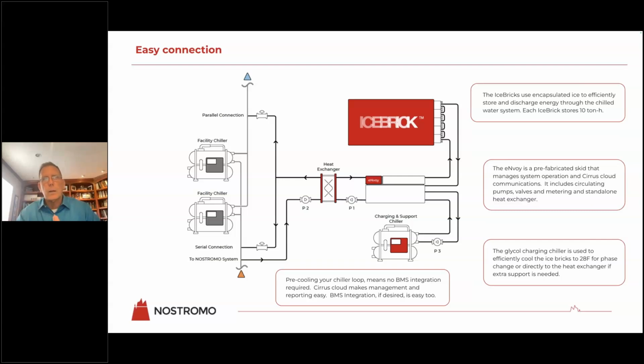Having this extra backup charging chiller would be like an N+1, and then the IceBricks would be an N+2. In some cases, maybe you've got an older chiller or a couple older chillers - we have many applications like that. You've got a 20 or 30-year-old chiller, it's at the end of its life and you need to replace it. So what you would do is go out and spend $500,000 on a new chiller. Instead, maybe you spend that same money and get a chiller and an energy storage system backed up, automated, and with grid revenue, because it's all part of that.